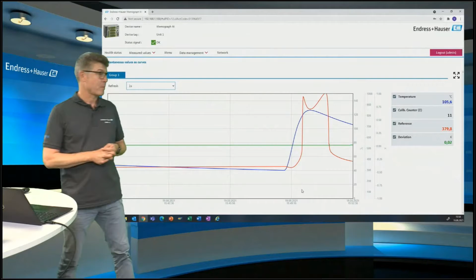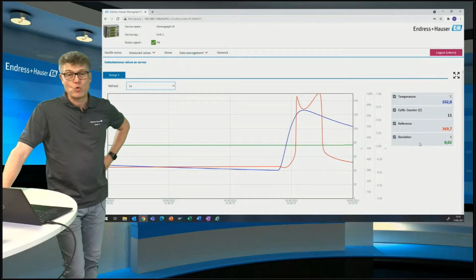When we go back to the screen, we see we have performed the 11th calibration, and the result of the calibration was 0.02 degrees of deviation. To make you understand, the acceptable tolerance of a double class A sensor together with a high class temperature transmitter would be 0.4. So 400 millikelvin instead of 20 millikelvin here.